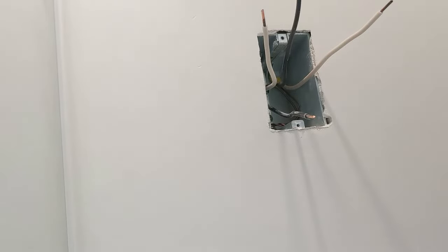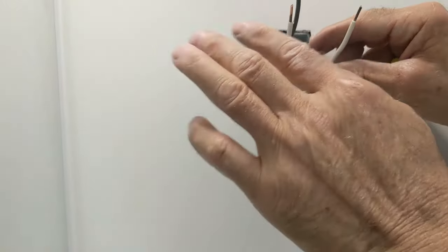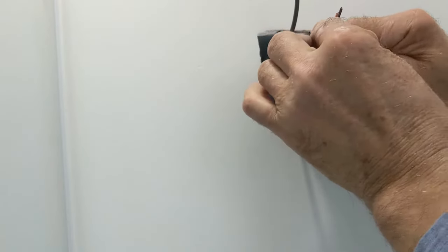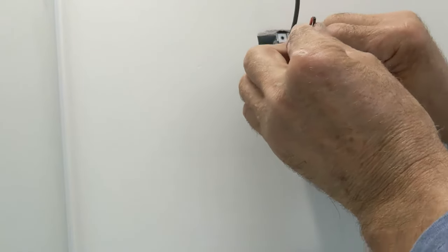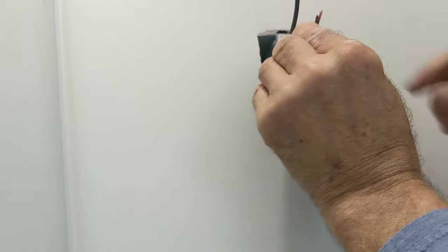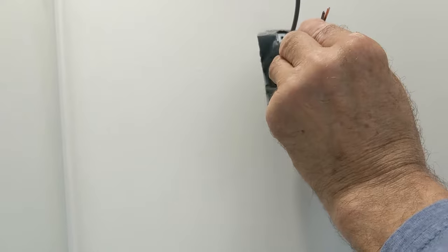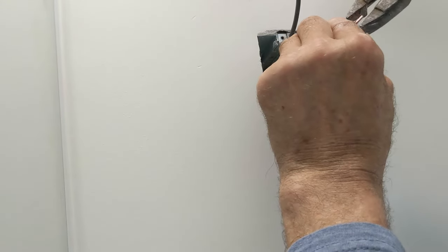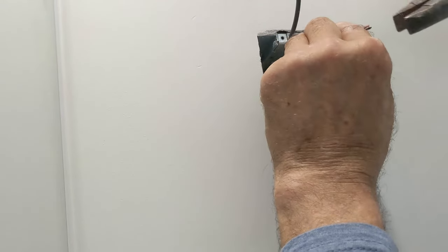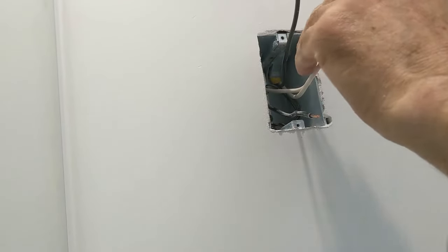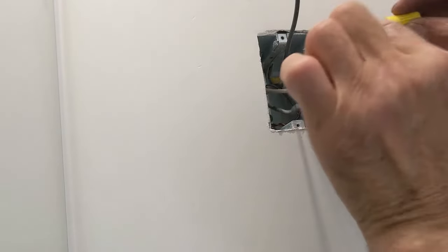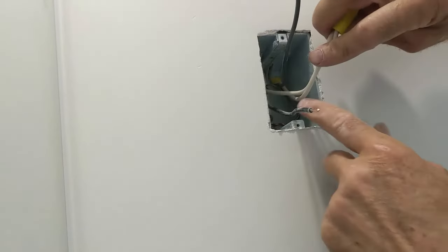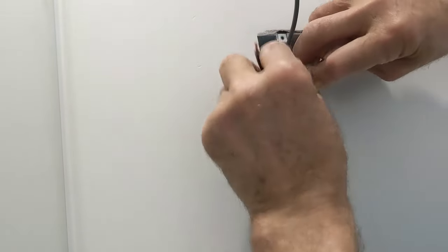So what I'm gonna do, these are both hot wires, so this is a single pole thermostat. So this one, let's just connect this guy straight. Just like you guys can see, this is a 12 gauge wire. Once I have this in here I'm just good to go. This guy here is done.